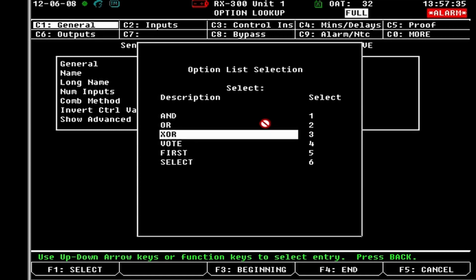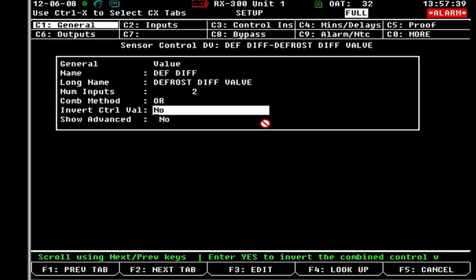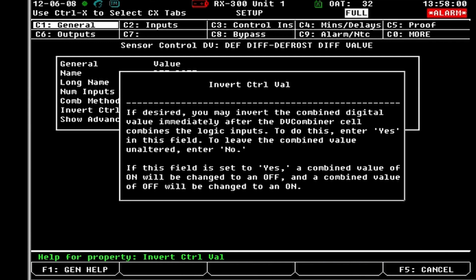So with this one, we're going to go with OR. Okay, so you can invert control value, meaning the control value could be backwards. So whatever you need it to be. So if you had 2 things that were on all the time and you needed them to be off to make it be on, you can invert the control value that way. And if you look at the definition for this: if desired, you may invert the combined digital value immediately after the digital combiner cell combines the logic inputs. To do this, enter yes. This field will leave combined values unaltered if no. If this field is set to yes, combined values of on will be changed to off, and combined values of off will be changed to on. Meaning it'll just switch around whatever it is, whether it's on or it's off.